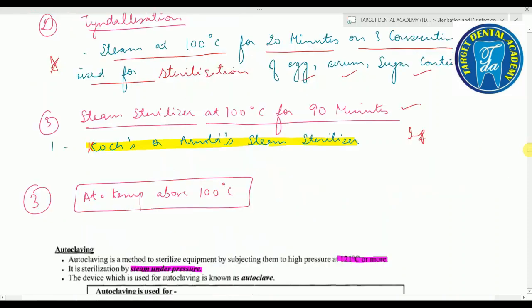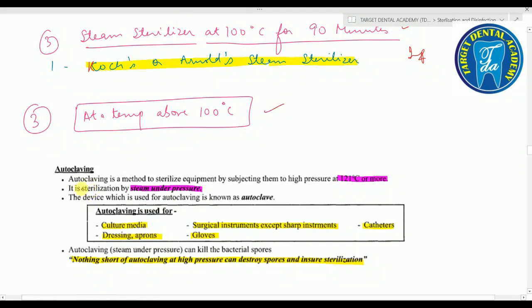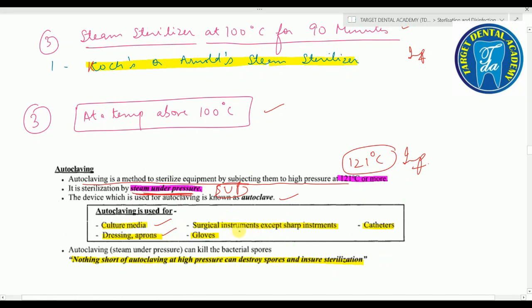At temperature above 100°C, you use the autoclave. Autoclaving sterilizes equipment by subjecting them to high pressure steam at 121°C — sterilization by steam under pressure. The autoclave is used for culture media, dressings and aprons, surgical instruments except sharp instruments, gloves, and catheters. Autoclaving under high pressure can kill bacterial spores — nothing short of autoclaving can destroy spores and ensure sterilization.